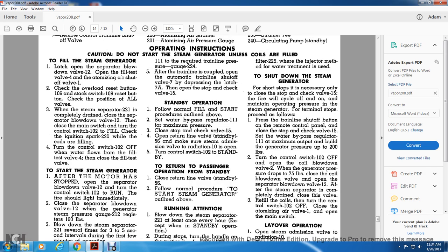After the train line is coupled, open the automatic train line shutoff valve 7 by depressing the latch at 7A. Then open the stop and check valve 15 and follow the normal fill and start procedures outlined above. Set the water bypass regulator for maximum pressure. Close the stop and check valve 15. Open the return line valve with the standby 56. Make sure the steam admission valve with the radiation 10 is open. Turn the control switch 102 to standby. Return to normal operation from standby. Close the return line valve standby 56. Follow the normal procedures to start the steam generator outlined above.